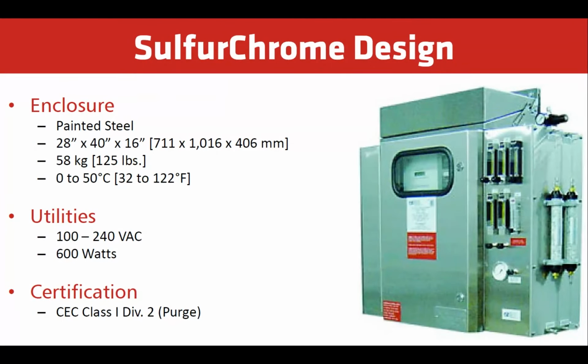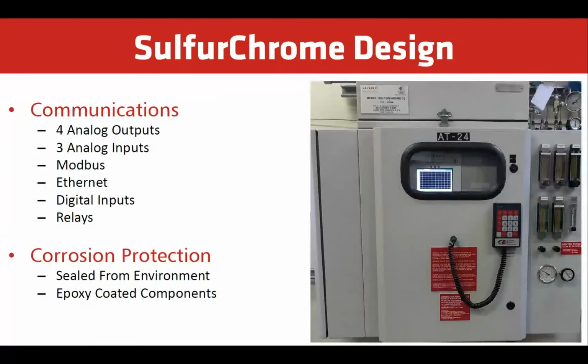It weighs 125 pounds, with a 0 to 50 degrees C ambient operating temperature. For electrical utilities, 100 to 240 volts AC, 600 watts. The certification is a Class 1 Div 2 purge system. The Sulfur Chrome design. For communications, we have 4 analog outputs, 3 analog inputs. It has Modbus, Ethernet capability, digital inputs, and relays.